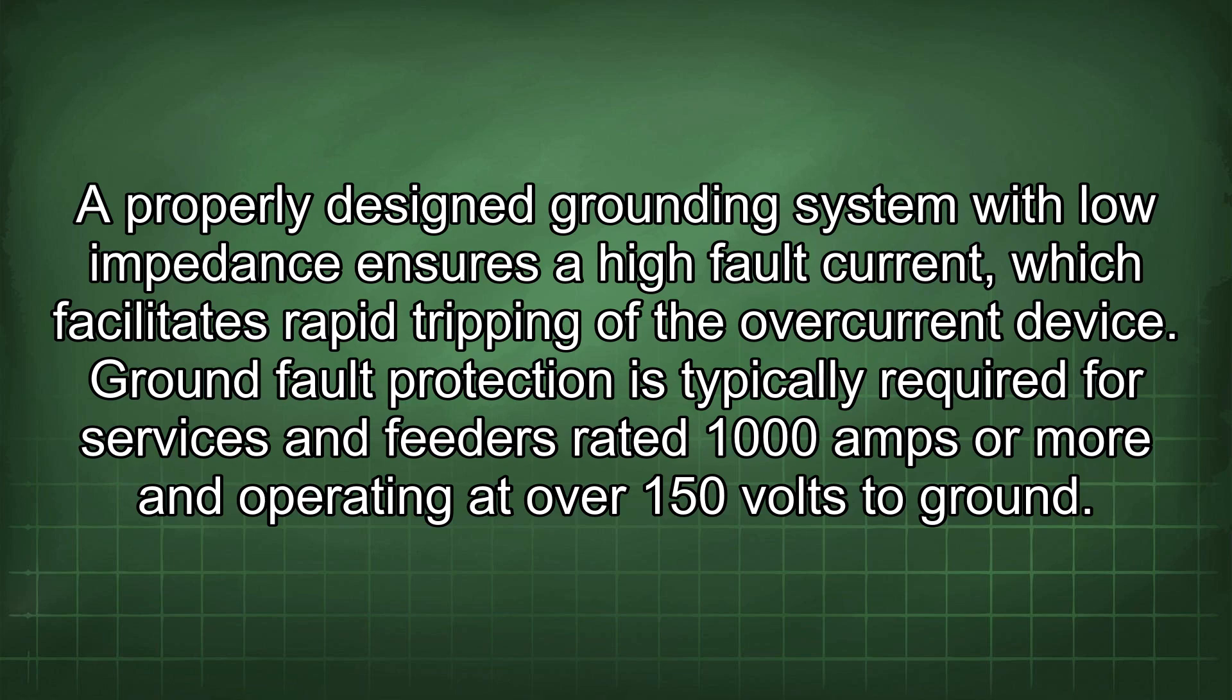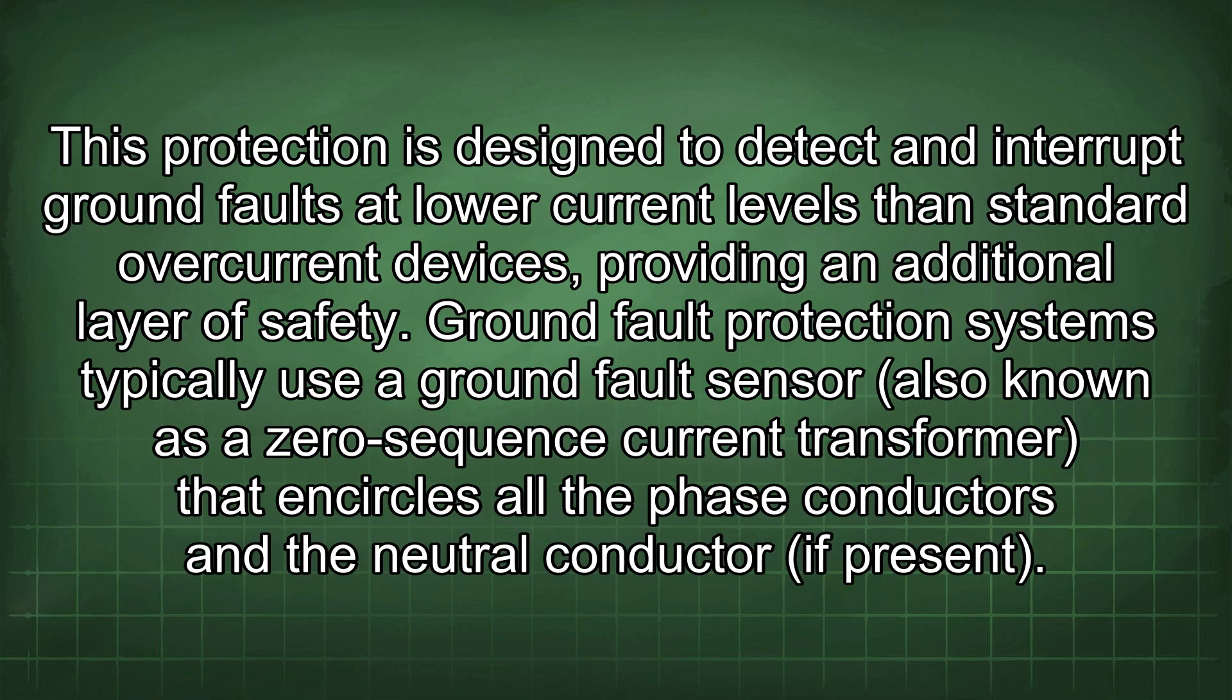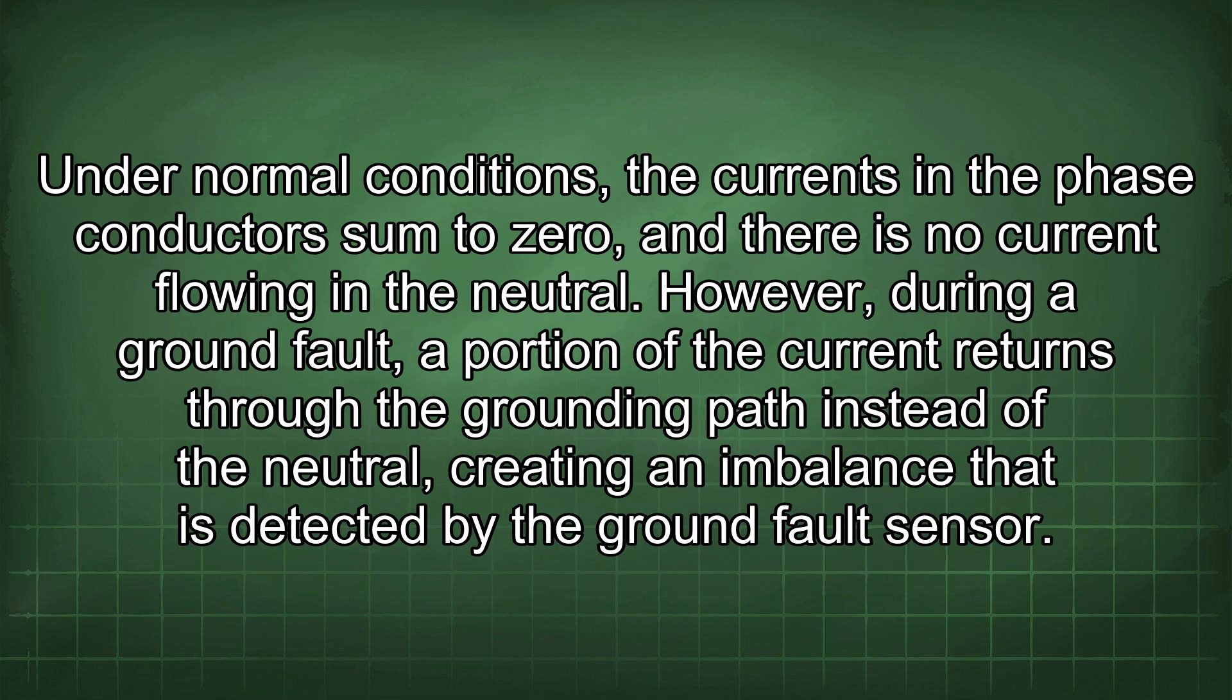Ground fault protection is typically required for services and feeders rated 1000 amps or more and operating at over 150 volts to ground. This protection is designed to detect and interrupt ground faults at lower current levels than standard overcurrent devices, providing an additional layer of safety. Ground fault protection systems typically use a ground fault sensor, also known as a zero sequence current transformer, that encircles all the phase conductors and the neutral conductor if present.